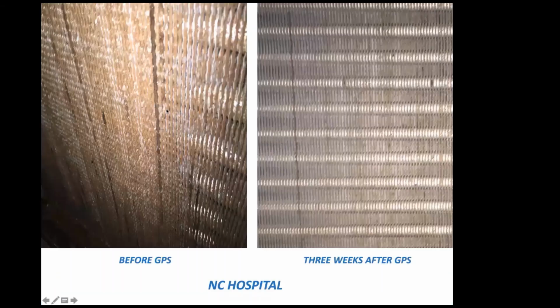And here's an example of a hospital down in North Carolina that had yellow mold growing everywhere on this cooling coil. And this was actually feeding the operating rooms, but they said they had HEPA filters downstream and they weren't concerned really about the mold. They actually put this technology in to control fumes from a new helipad as well as a loading dock with some diesel trucks that were idling.